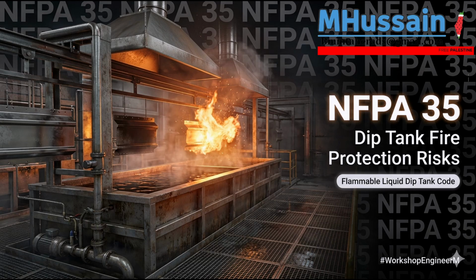Oh, wow. If a single spark is generated by static electricity, or if there is mechanical friction in a valve, the entire piping system instantaneously becomes a pipe bomb. Literally a pipe bomb. Yes. The standard mandates that you must use inert gas systems, like nitrogen or argon, for these transfers. Because it displaces the oxygen. Right. The inert gas pushes the liquid just as effectively, but it chemically displaces all the oxygen, rendering the environment completely non-ignitable, regardless of sparks. That is a crucial distinction for process engineers. Specify nitrogen, never air. Never air.